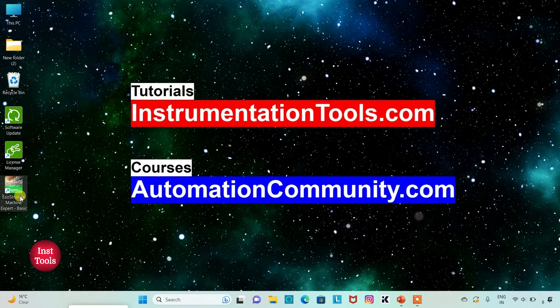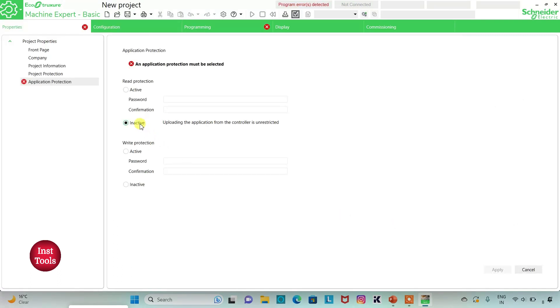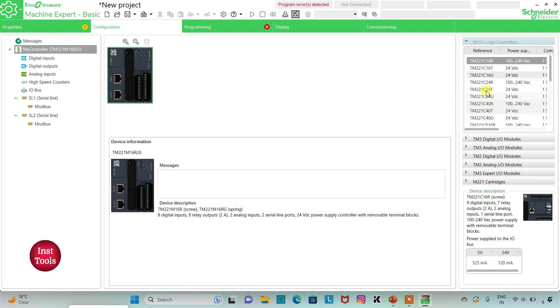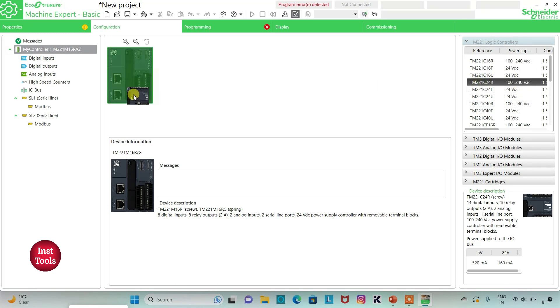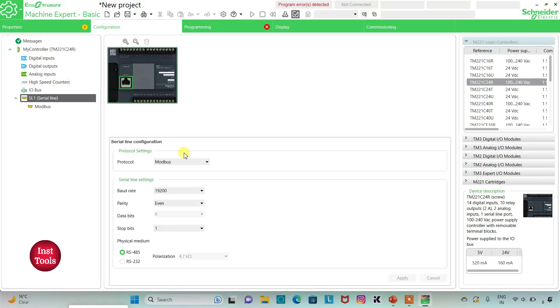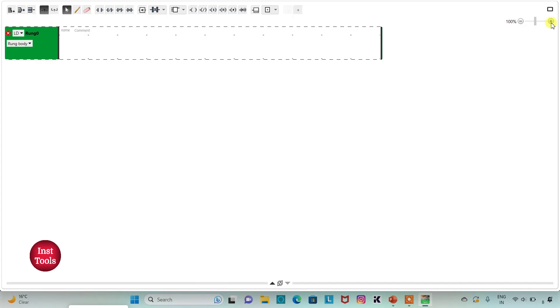I will open EcoStruxure Machine Expert Basic. I will keep read protection as inactive and write protection as inactive as well, then click on apply. I'll go to the configuration tab to select a logic controller — I will select TM221C24R and drag it in. I can also go to serial line, select protocol as Modbus, and click apply. Then I will go to the programming tab where I will draw the ladder diagram, switching to full screen mode and zooming in.